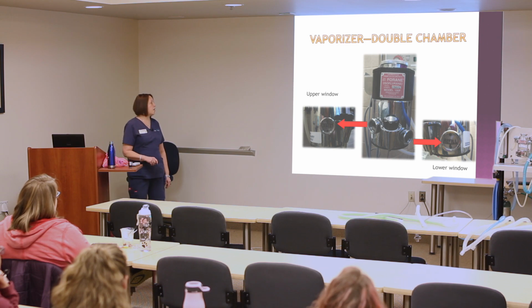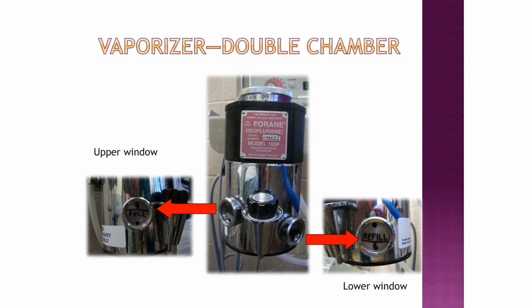Here's one of those double chambers. So they actually have two windows. The lower window is where the refill button is. The upper window is where it says full. And you know, I don't recommend that you overfill these, because if you're trying to fill this to the tippy top, and you have this cap open, what's going to happen is the liquid's going to come out the side. And to be honest, if you can smell your inhalant, you've already exceeded the amount that OSHA wants us to be able to smell. You're smelling more than 50 parts per million, and they really don't want you to smell more than 2 parts per million, which you wouldn't be able to smell at all.